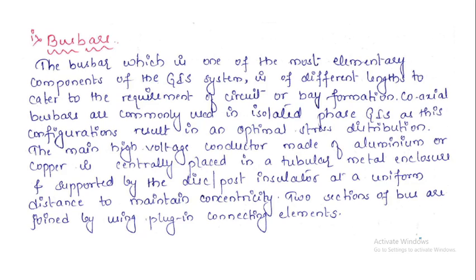The main high voltage conductor, made of aluminum or copper, is centrally placed in a tubular metal enclosure and supported by a disc or post insulator at a uniform distance to maintain concentricity. Two sections of the bus bars are joined using plug-in connecting elements. So this is about the bus bars, which will be receiving the incoming lines.